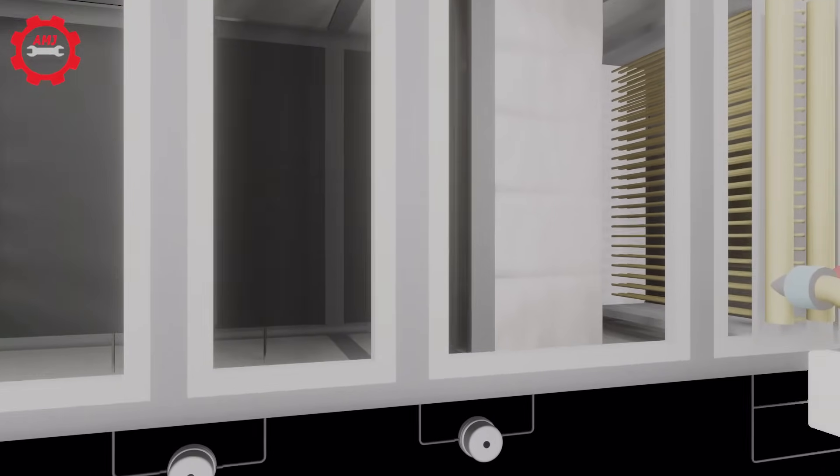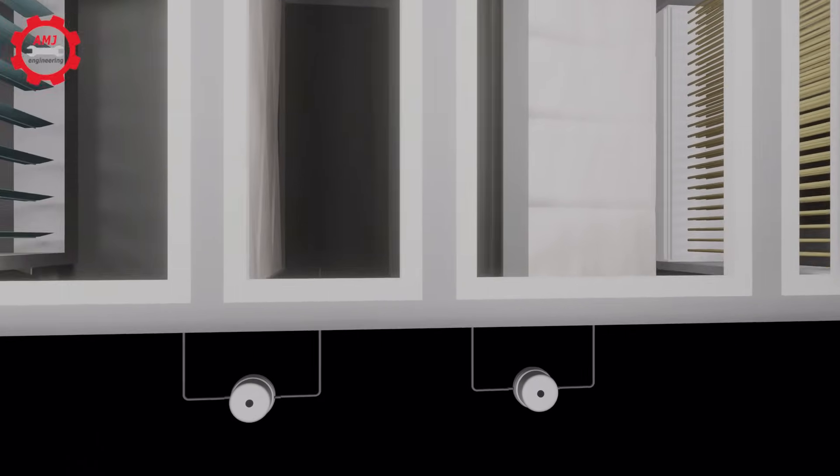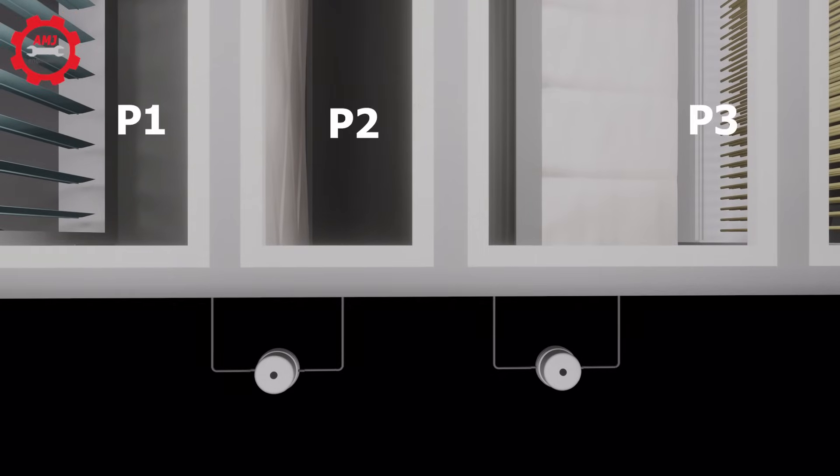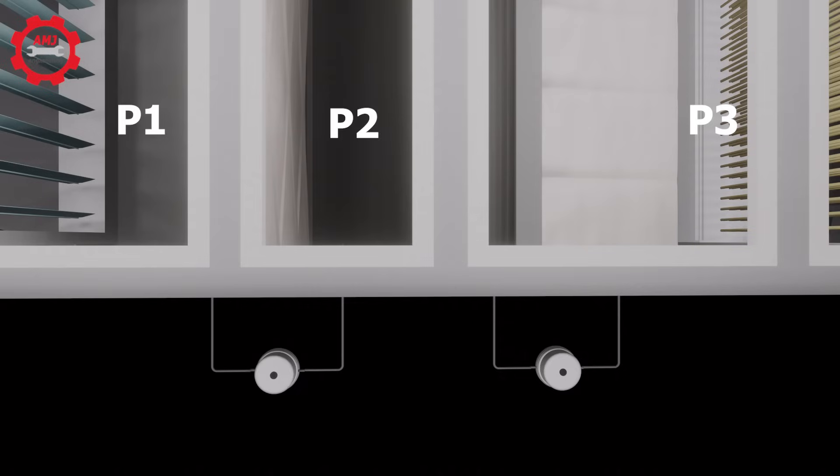Some air handlers include differential pressure monitoring devices to measure the pressure drop across the filters. The dirtier a filter gets, the higher the pressure drop, which results in reduced airflow.